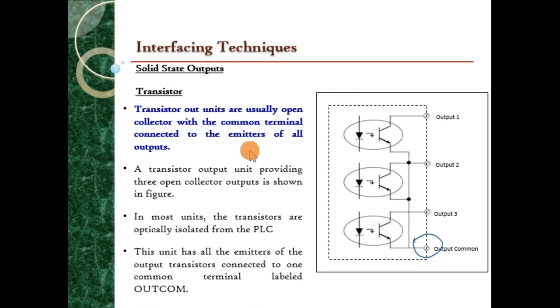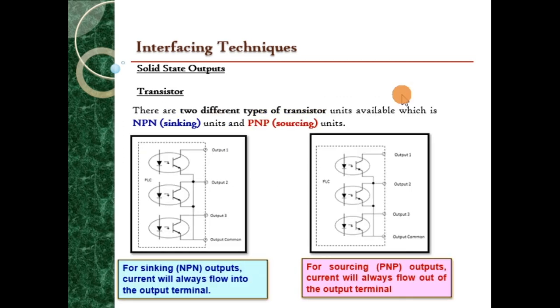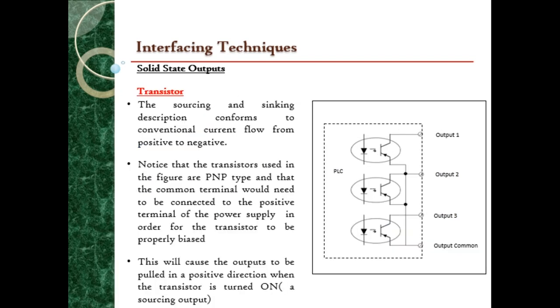labeled OUTCOM here. So the transistor that is used in the solid state outputs can be either NPN for sinking outputs or PNP for sourcing outputs. For sinking outputs, the current will always flow into the output terminal. While for sourcing outputs, the current will always flow out of the output terminal. The sourcing and sinking description conforms to conventional current flow from positive to negative.